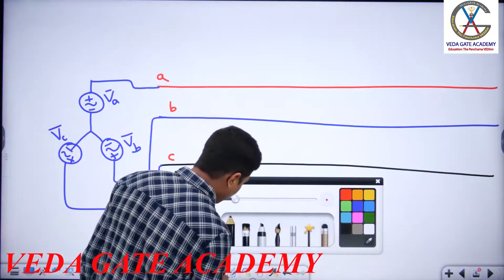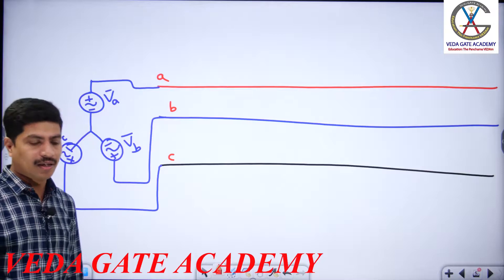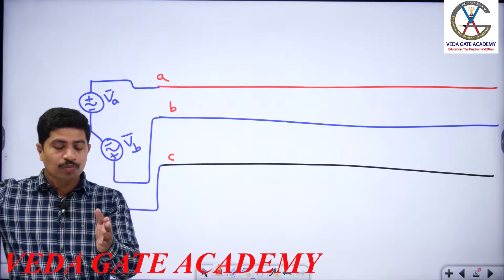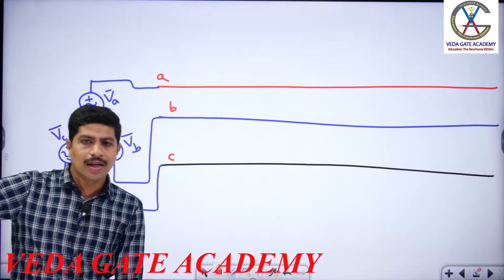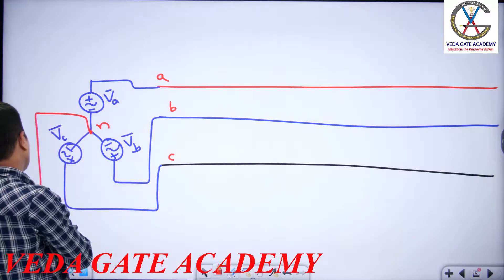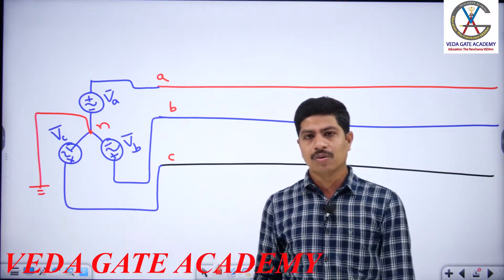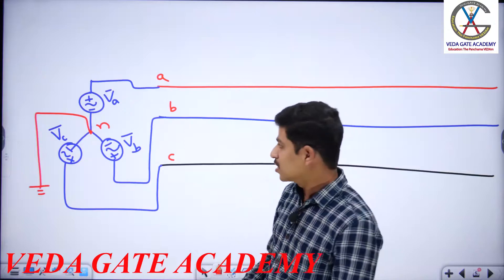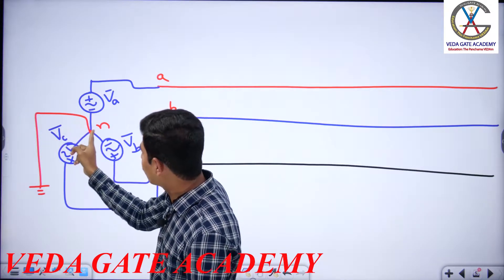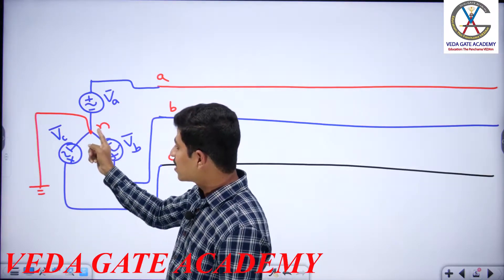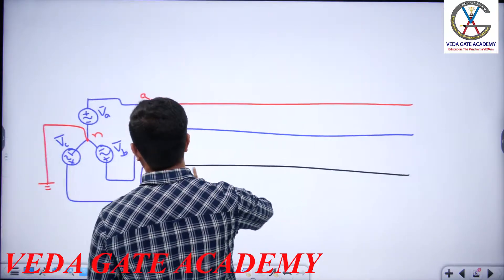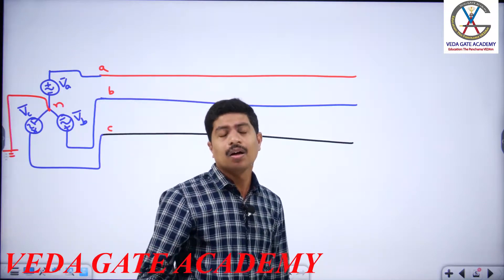You might be thinking: why have we taken only a star-connected generator and not a delta-connected generator? Remember: the generator always must be star connected. The reason for this we are going to understand in fault analysis. The point where all three phase wires meet is called the neutral. Connecting the neutral to the ground is called neutral grounding. Methods include resistance grounding, reactance grounding, and solid or effective grounding.